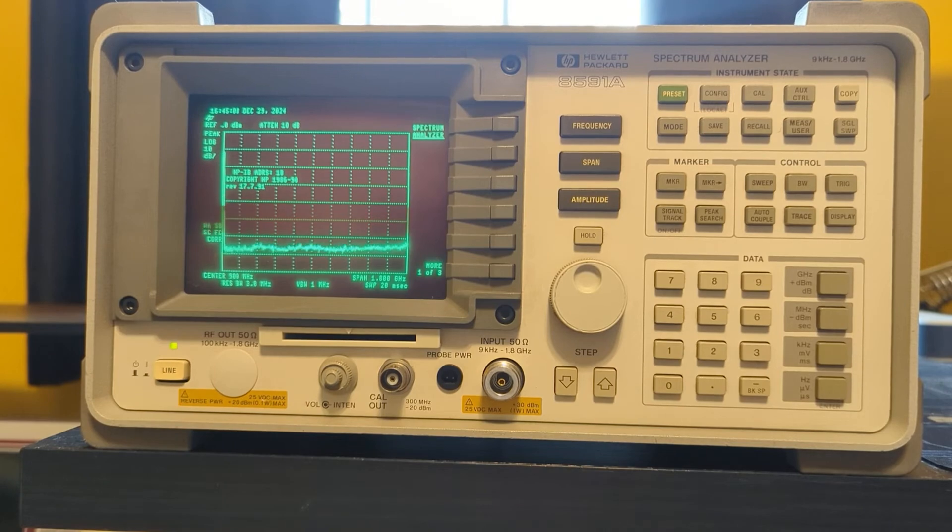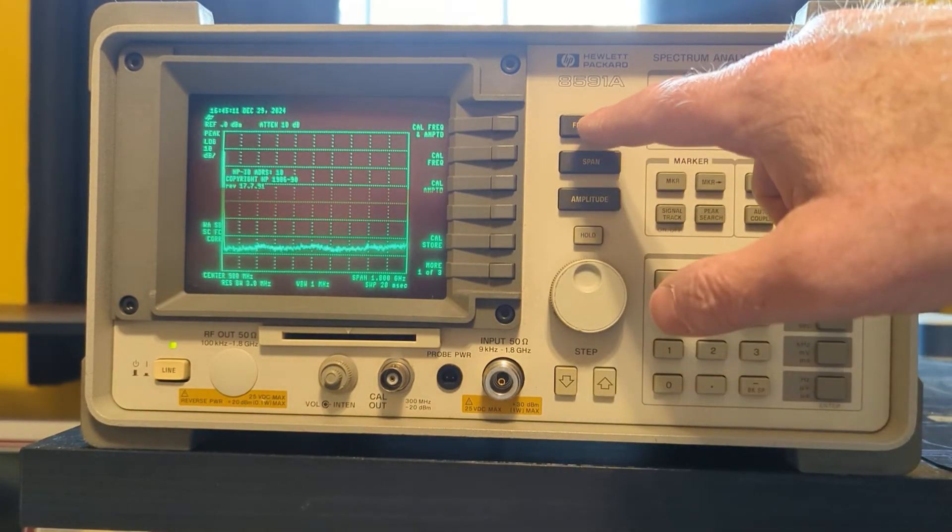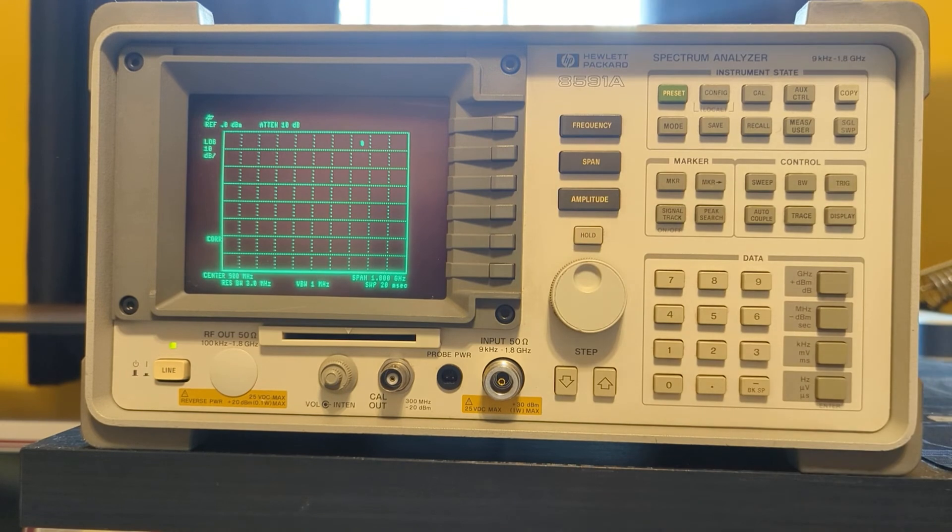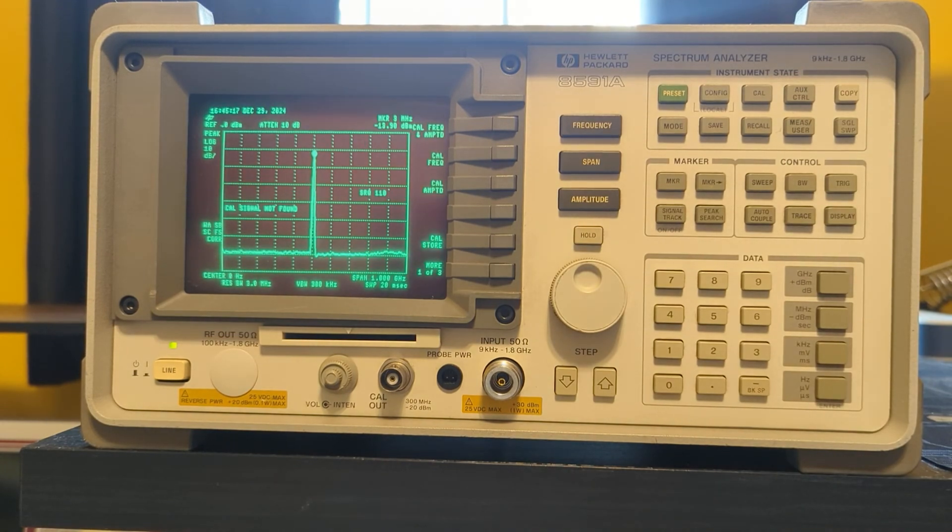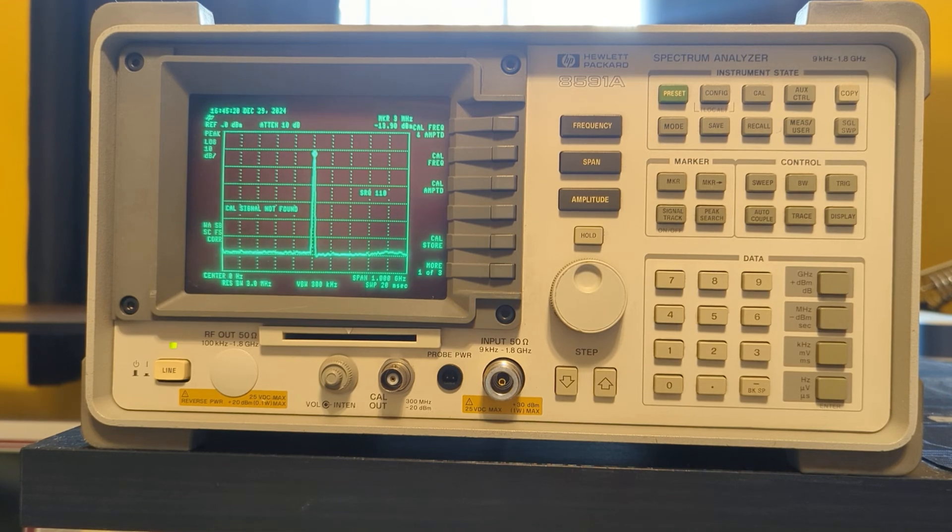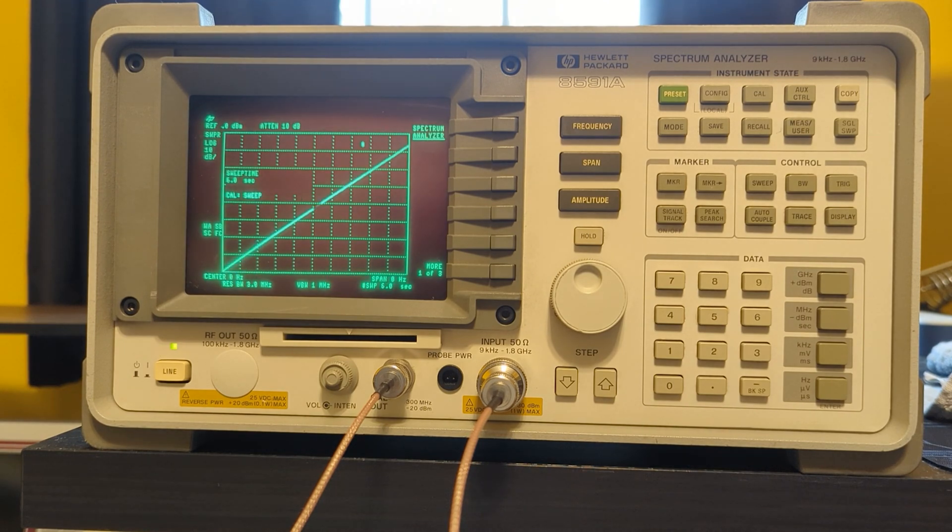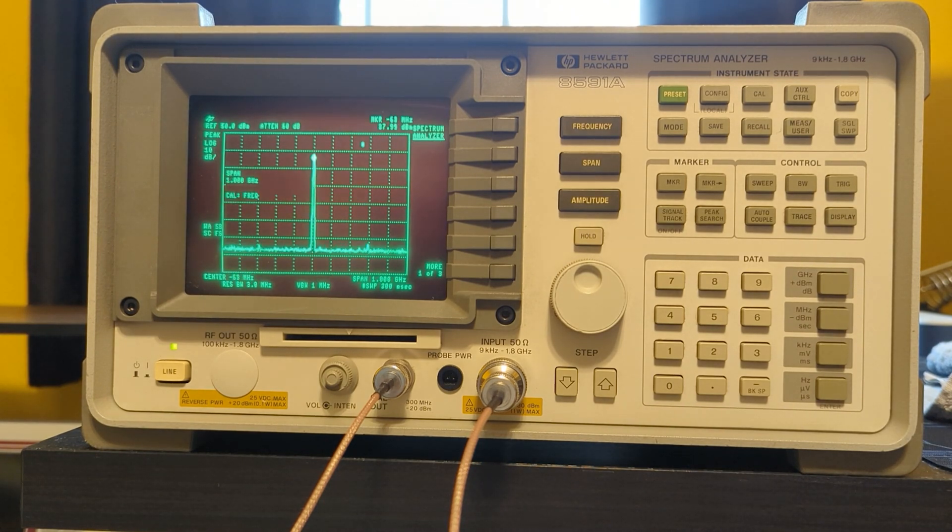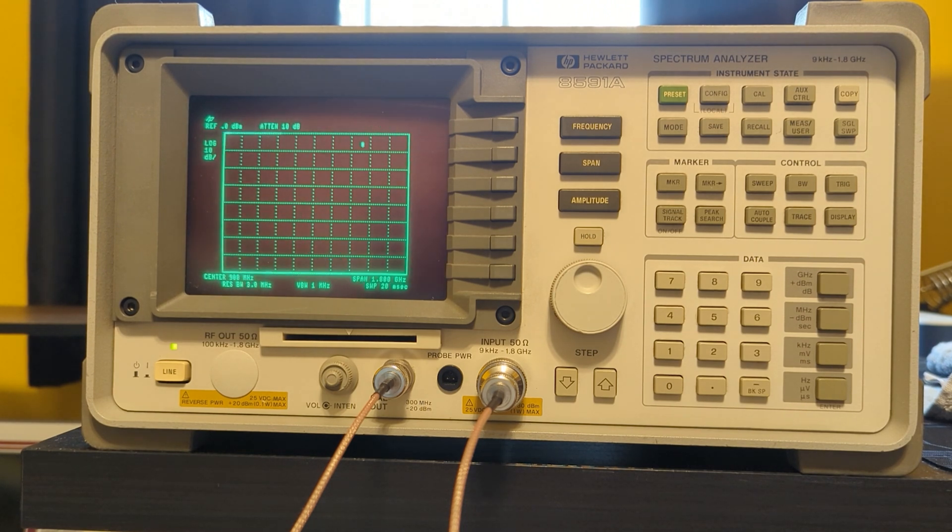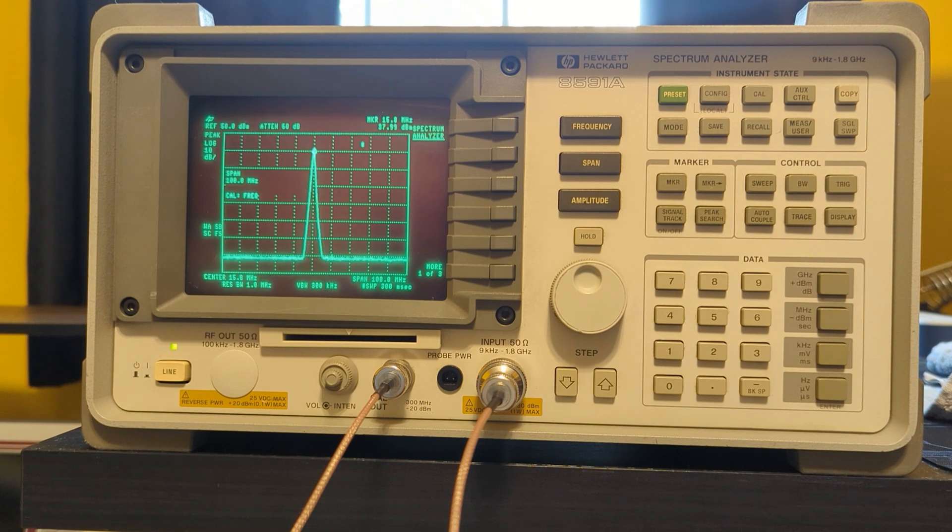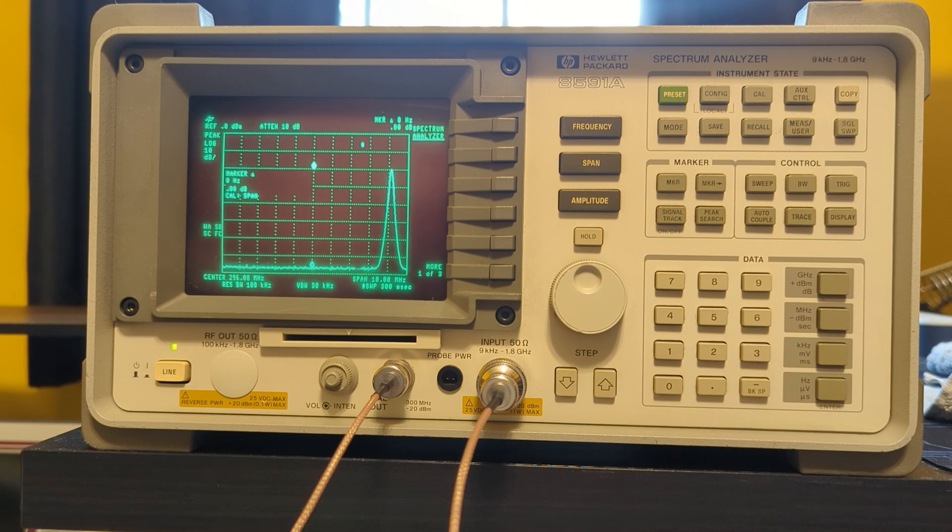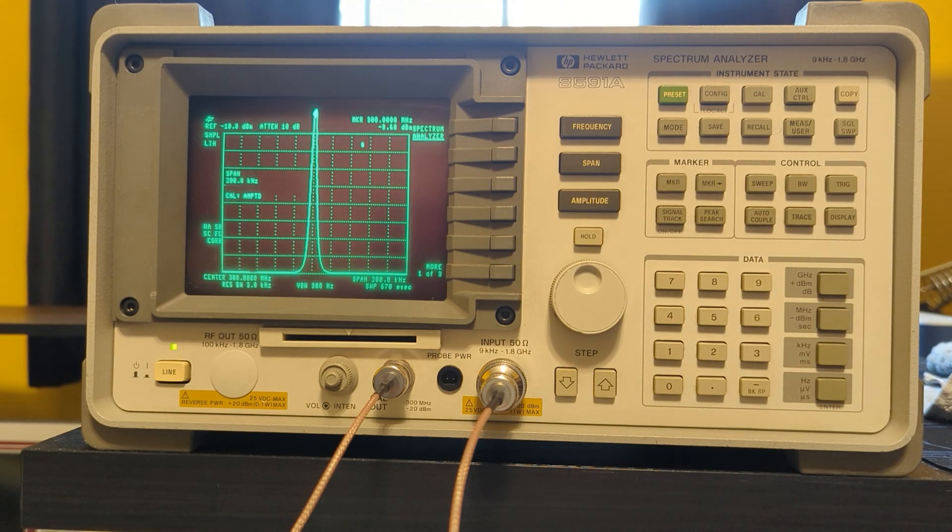Here's me trying to calibrate. You can see I go through the steps, but for those that know what's going on here, it's clearly not going to work because I don't have the calibration output connected to input. With the cable connected, I'm going to go really fast here because this calibration takes a while, but I did want to record all of it for the 8591A. The trick is once it's done, I have to push Cal again and then say store. That will actually save it in the thing.